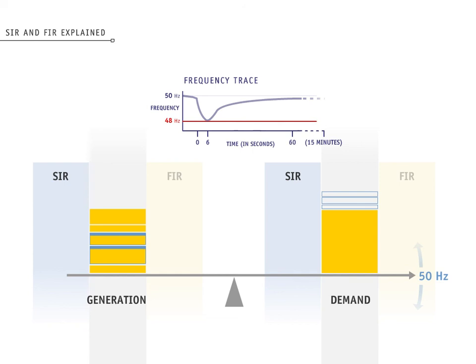Now that the FIR and SIR have restored the balance, generation is re-dispatched to release the SIR after 15 minutes, and the return of the interruptible load then follows.